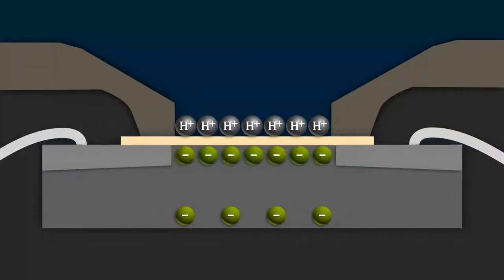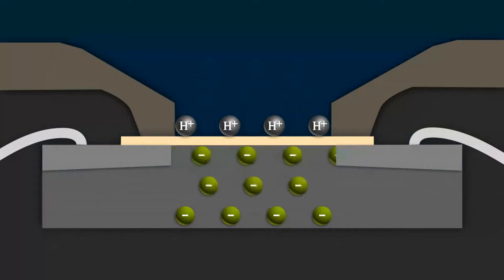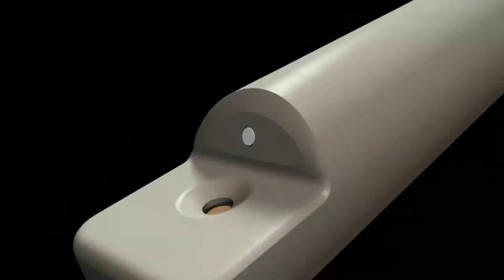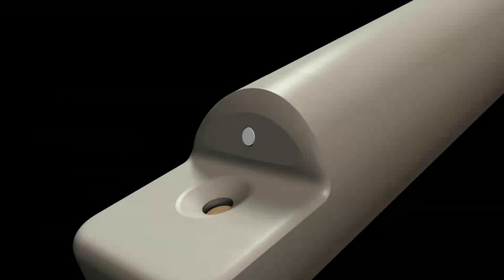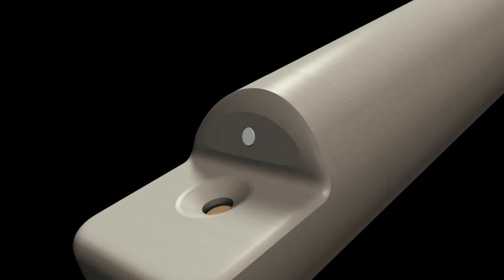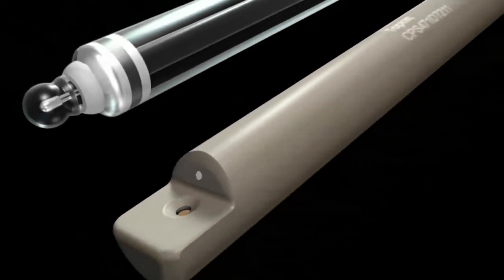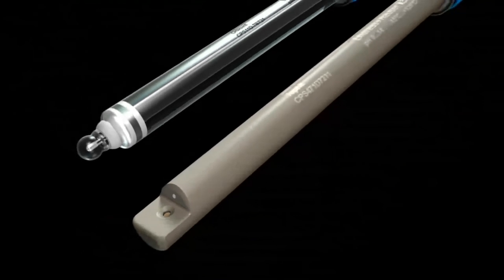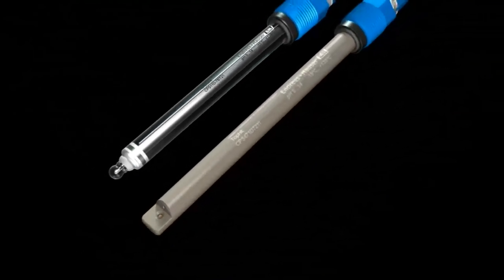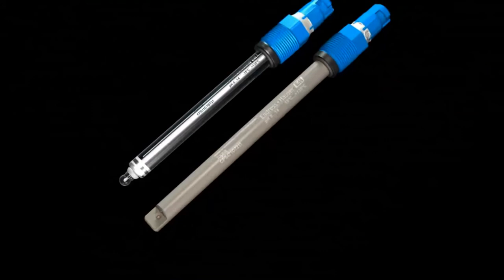The resulting flow of current is in direct proportion to the pH value of the media. Like glass sensors, the ISFET sensor also needs a stable reference potential. The potential that forms at the ISFET can then accurately be measured against it, with the reference system also protected from the measured solution by a junction. The potentiometric measuring principle enables highly accurate pH measurement for better product yields and less waste.